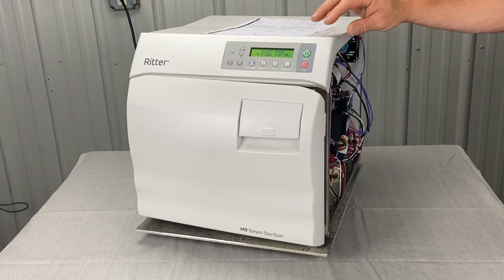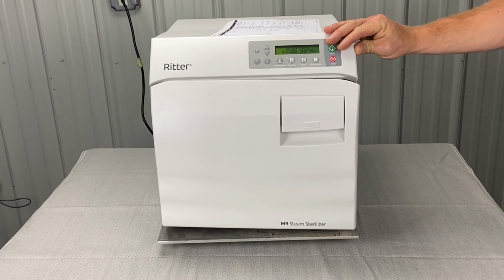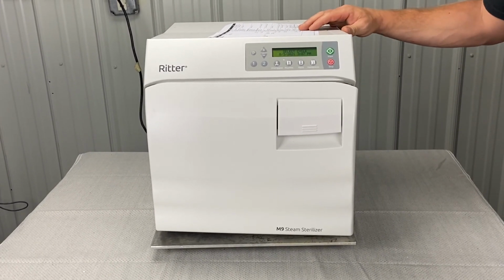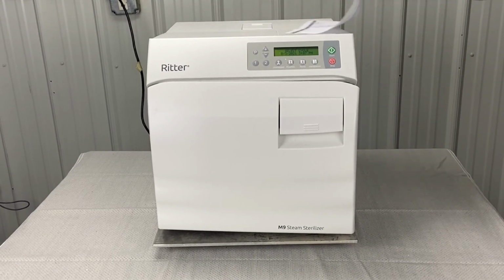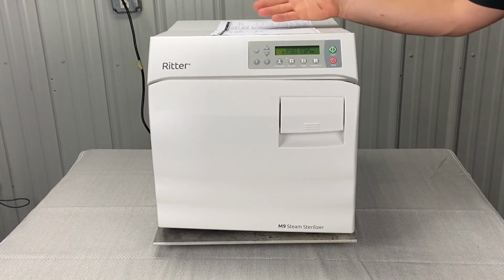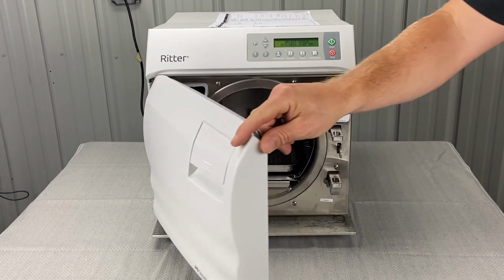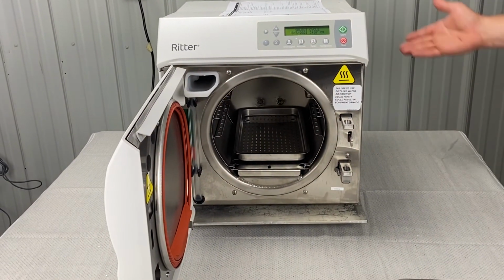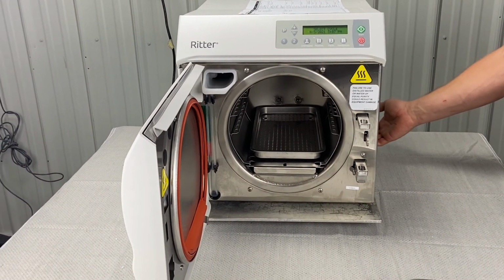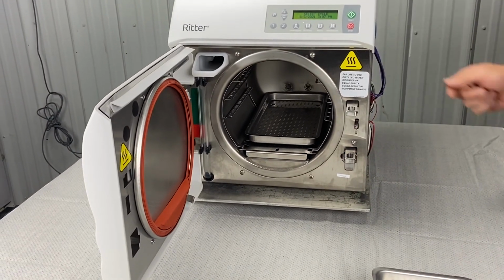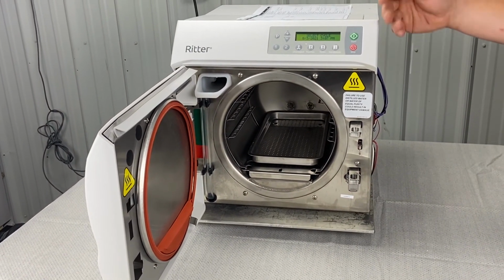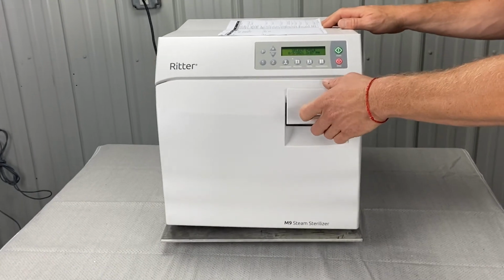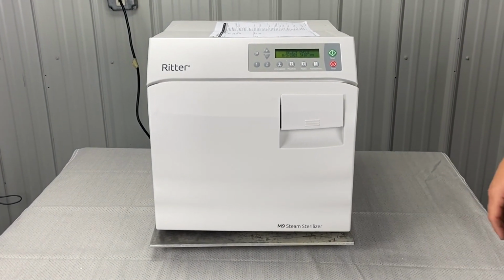So this is a pretty lengthy error code. Couple things: sterilizer's level, possibly the wall voltage you can check, and then any pressure leaks, door gaskets. Stay up on your maintenance, the pressure relief valve, make sure it's not leaking in the back corner here. If the air vent bellows is bad or something's clogged in the condensing coil, you're gonna have to take the whole cover off. So please give us a call.